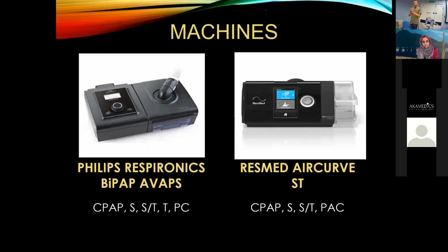So with your Respironics BiPAP AVAPS machine, ST mode is where you will find your AVAPS function as well. You can use ST mode traditionally, set the IPAP and set the EPAP, or it has an AVAPS function where you can set a volume control and then give an IPAP range. On the right, we have the ResMed AirCurve ST machine, which I think is on some of the pictures I've been sent. Modes of ventilation on this machine are CPAP, synchronized mode, ST mode, which is BiPAP, and PAC mode. Also on the ResMed AirCurve, IVAPS is a separate mode.